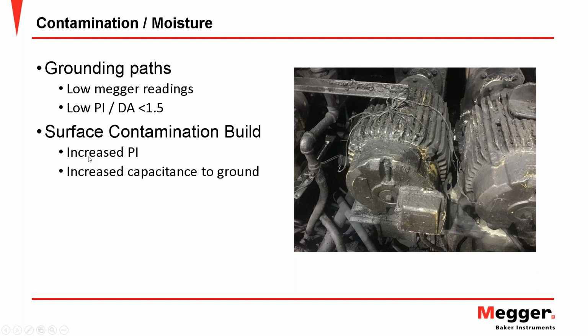Surface contamination buildup could have an effect of increasing PI if it increases the capacitance. So there's a little more to the evaluation of how we determine this. Depending on if that contamination creeps into the junction box, for example, that's effectively going to lower the PIs and lower the MEGGER readings. But there is a potential, just on the winding external, not to the electrical connections, but external to the insulation, to effectively increase the conductive path and the effective surface area of the coil, and the capacitance could increase, causing PIs to actually increase over time.